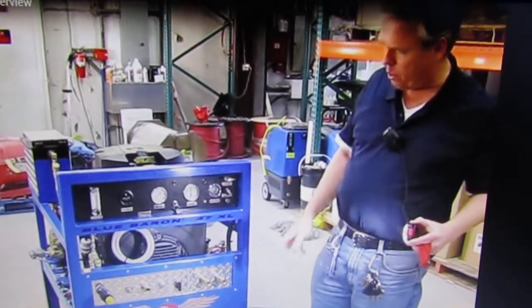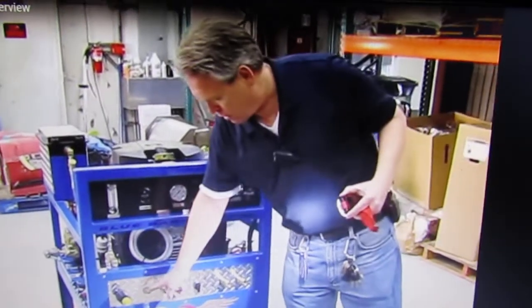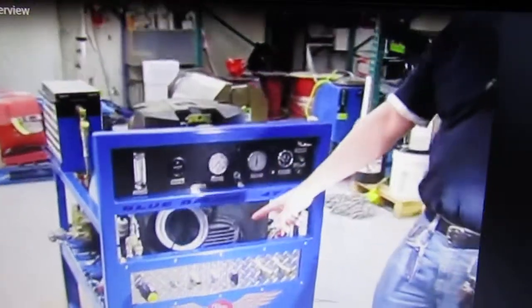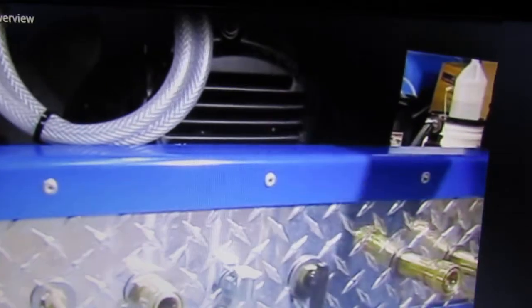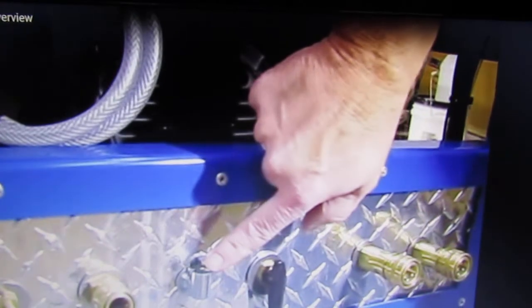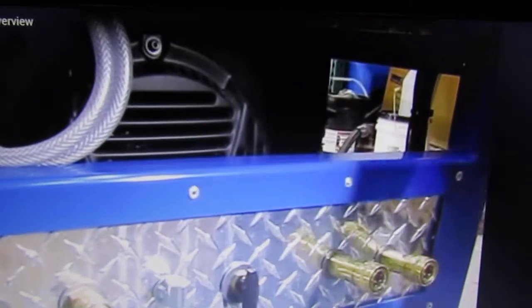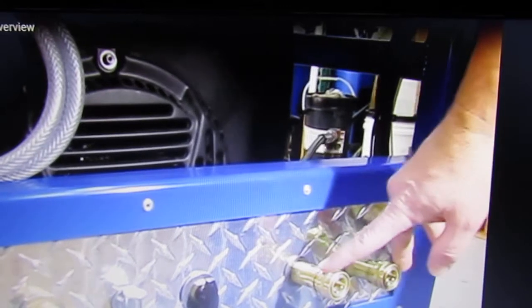On the front control panel, there's even this little barb fitting here, and that is a quick drain feature that is to set up and drain your water box in the event that you need to service the water box or even for freezing. This connection here is your garden hose connection on a quick disconnect. This is a vacuum pump oil breather port to help lubricate the blower to keep it from locking up on you. This is a chemical priming meter, and then it's a dual solution hose discharge.